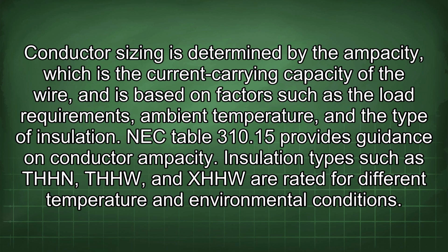Conductor sizing is determined by the ampacity, which is the current carrying capacity of the wire, and is based on factors such as the load requirements, ambient temperature, and the type of insulation. NEC Table 310.15 provides guidance on conductor ampacity. Insulation types such as THHN, THHW, and XHHW are rated for different temperature and environmental conditions.